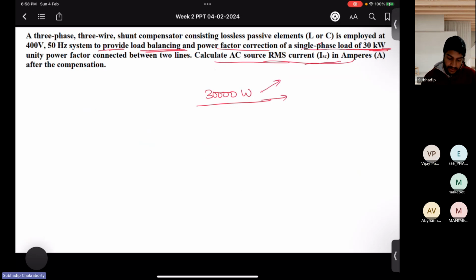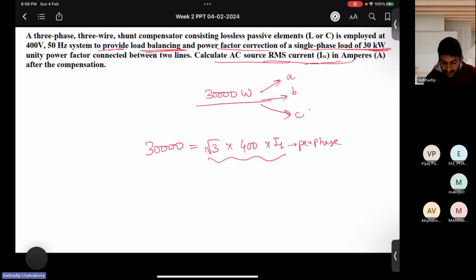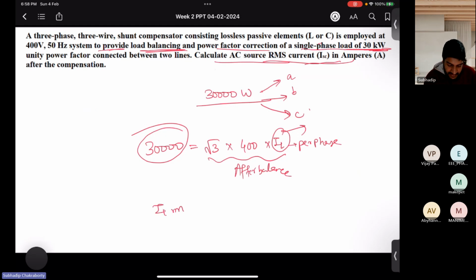Because this loading, after load balancing, will be split among A, B, and C. So do power balance. 30,000 is the net power, and it should be split at unity power factor equally among 3 phases. So √3 into VL into IL per phase after balancing. And it is unity power factor since you have done load balancing as well as power factor compensation. So net load is this, which will be split among the 3 phases after compensation at unity power factor, and then you can find out the IL value, IL RMS actually.